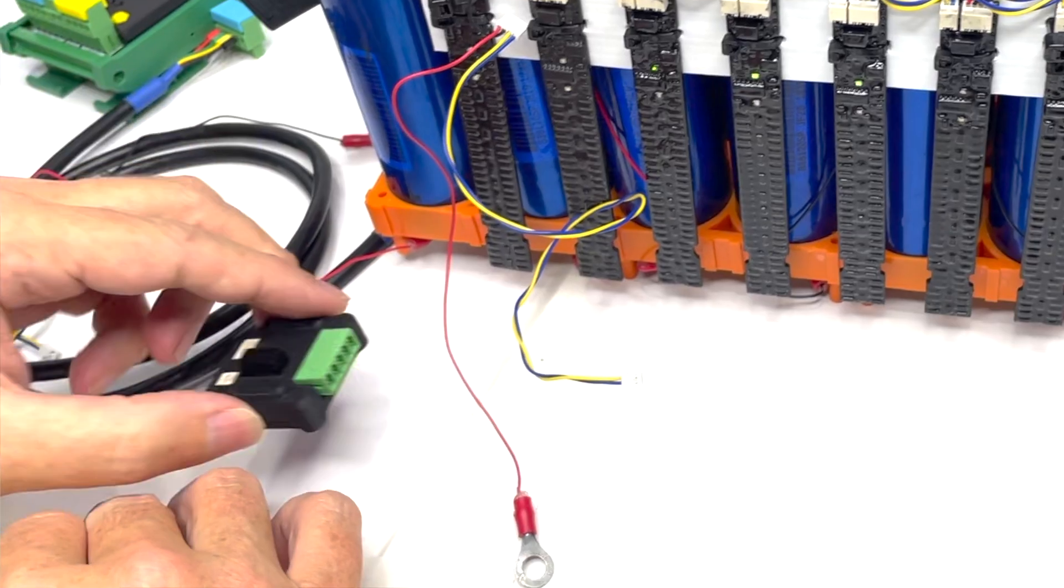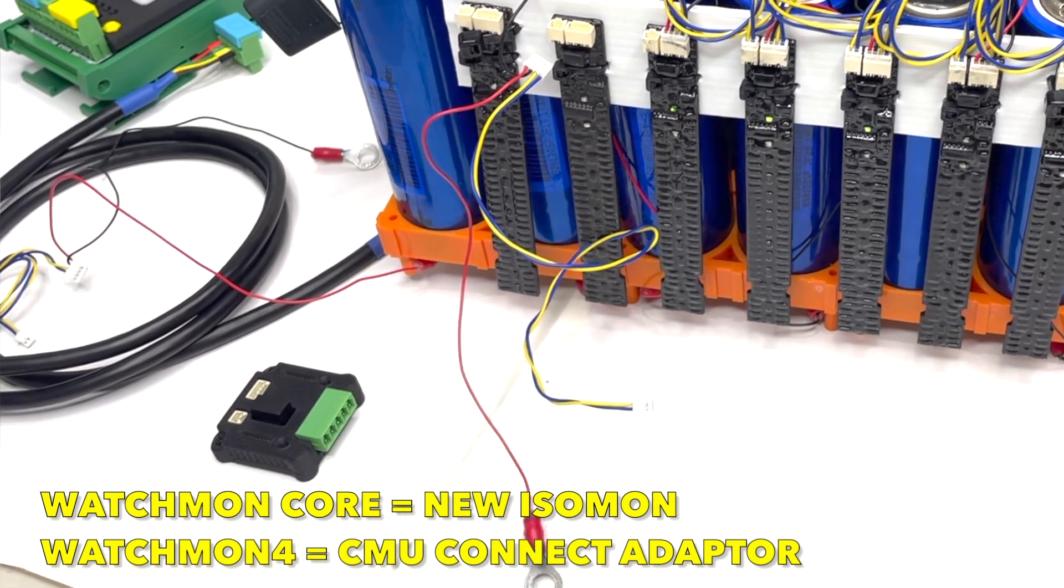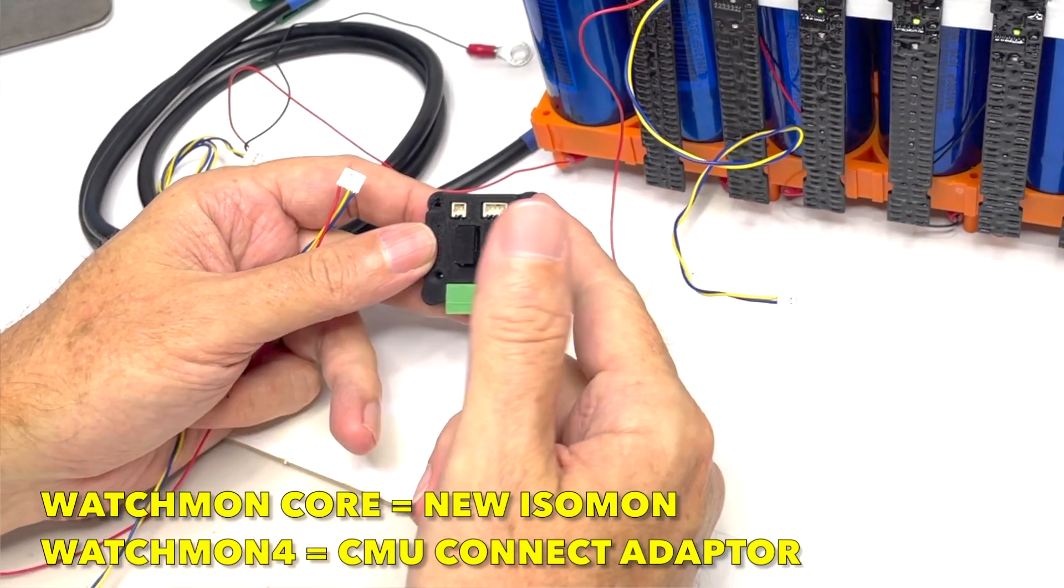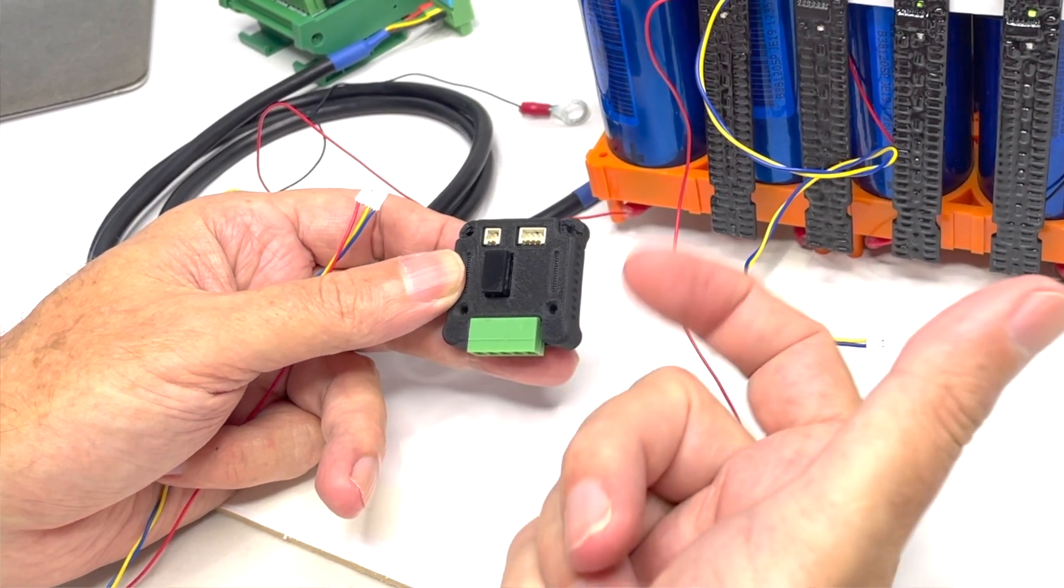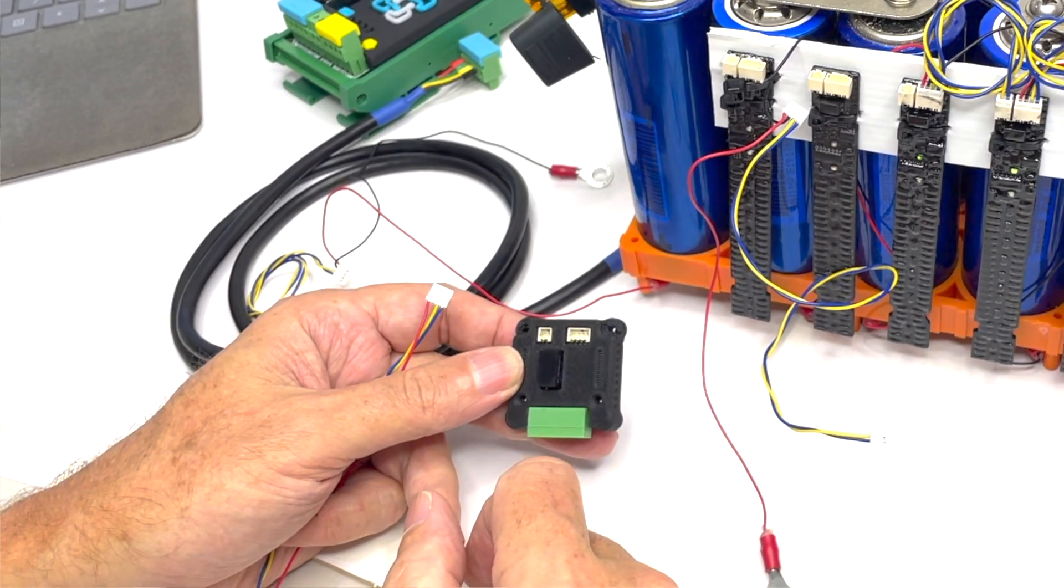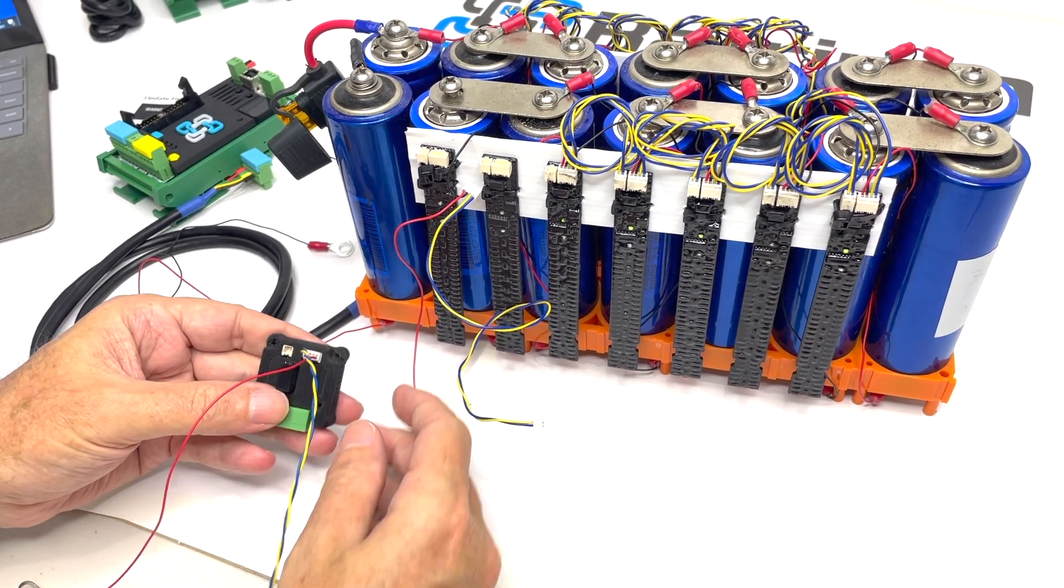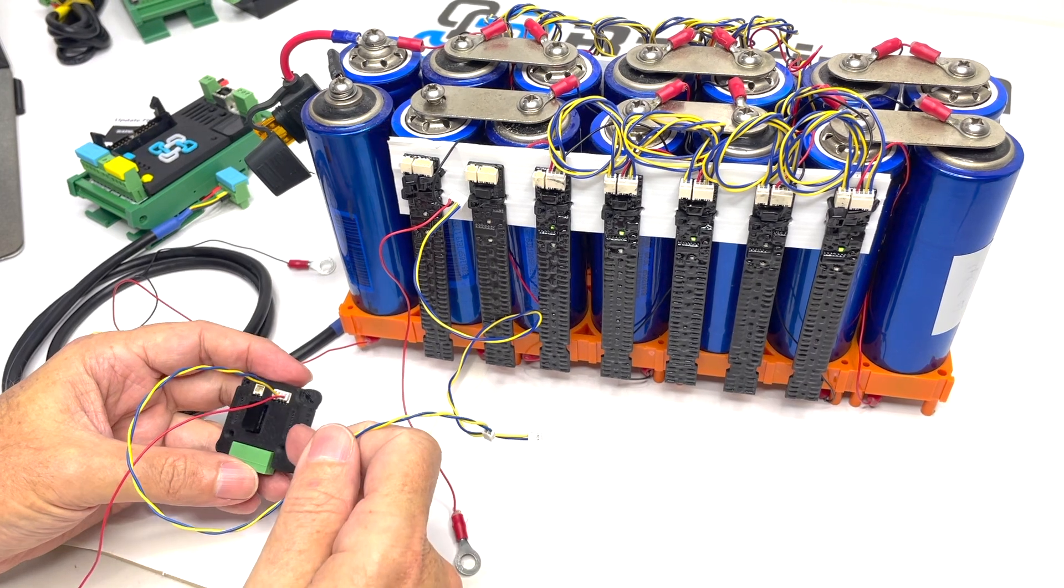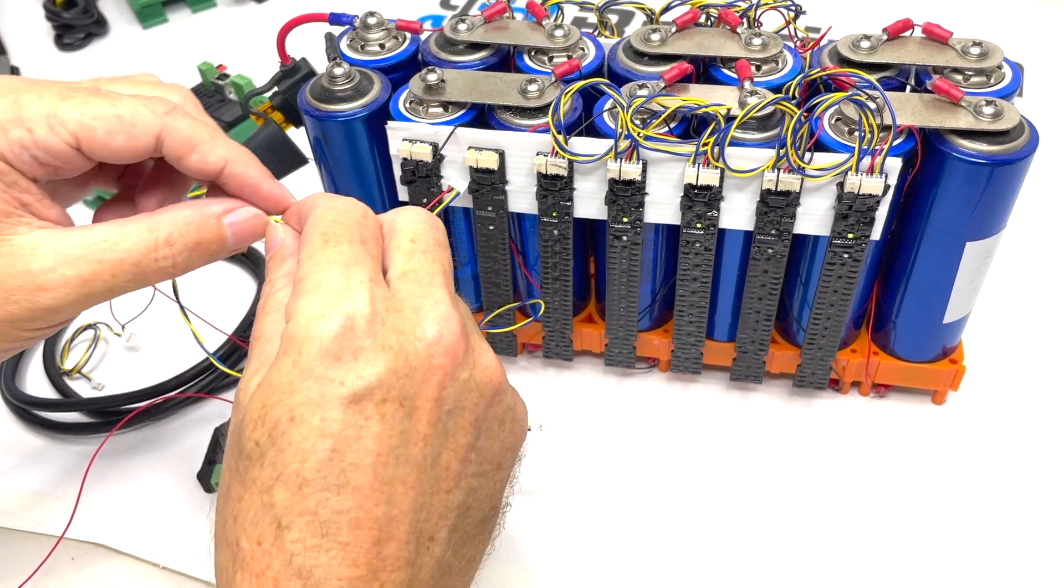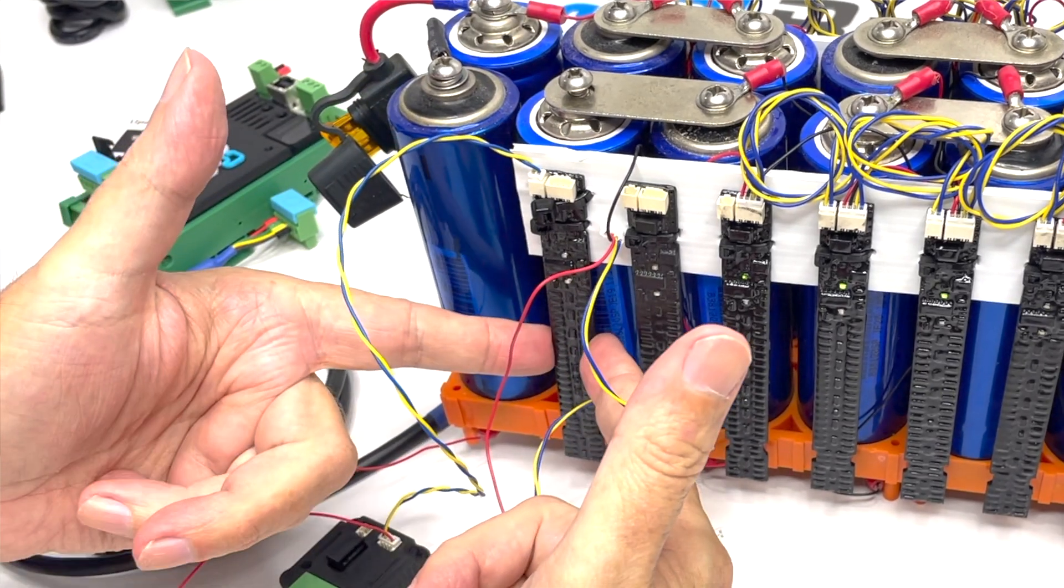We start with our IsoMon. Now with our IsoMon we start with a cable and in the case here we have a four pin and a two pin. The four pin is the transmitter and on our IsoMon we have this little red LED when we plug it in and connect it up further down the path that will transmit out of this device and communicate that it's actually trying to connect to the next device. So we'll plug this four pin in like so. Now in this particular case this four pin is transmitting out of the device which is the WatchMon isolation which is from the IsoMon and then we would connect it up to the two pin on the first WatchMon here. So that's this one here. So we then now know this would be cell one.